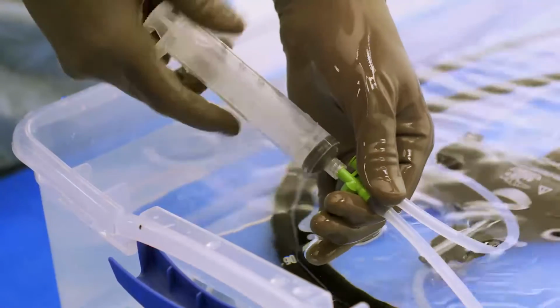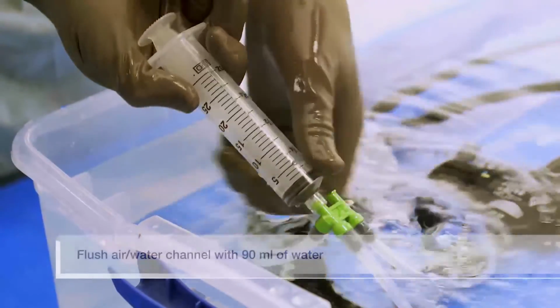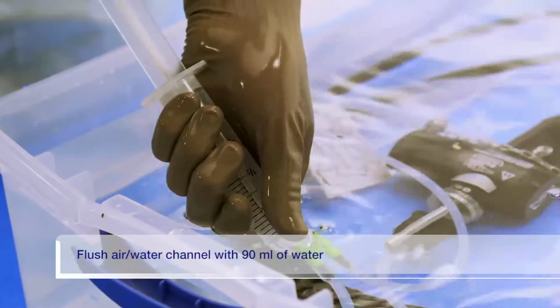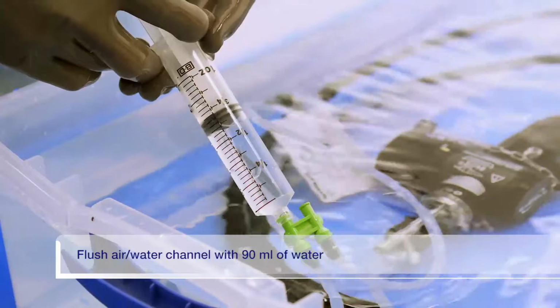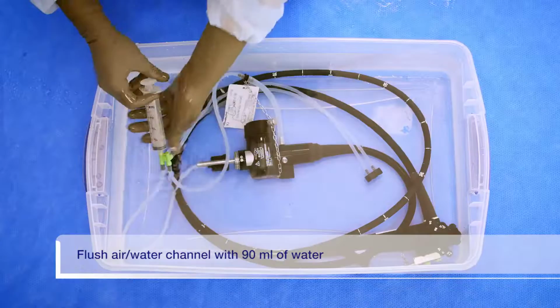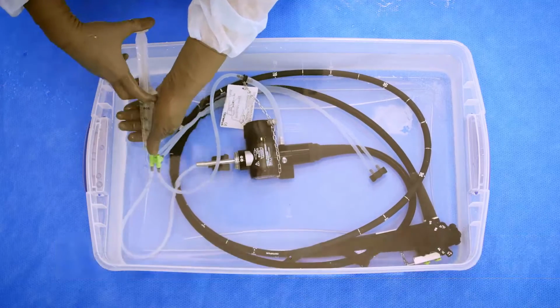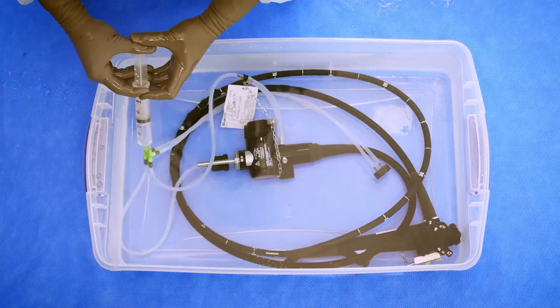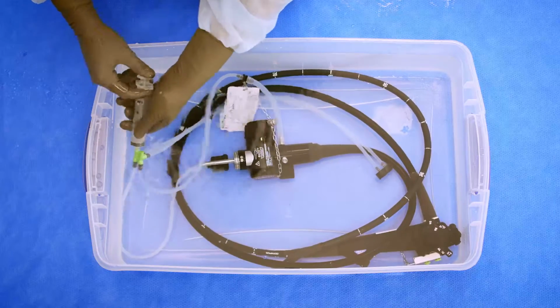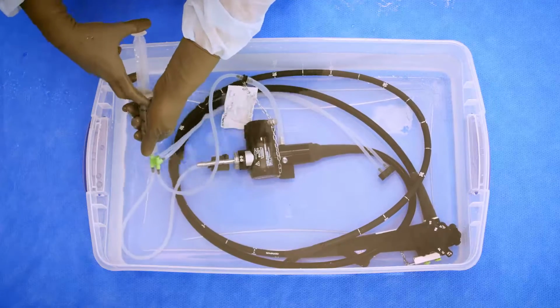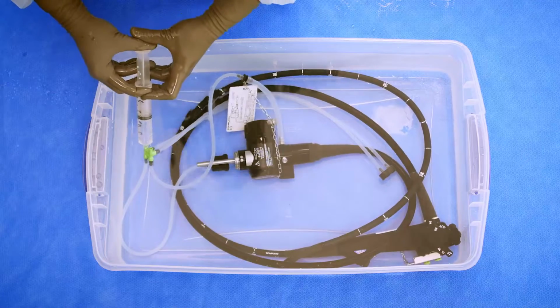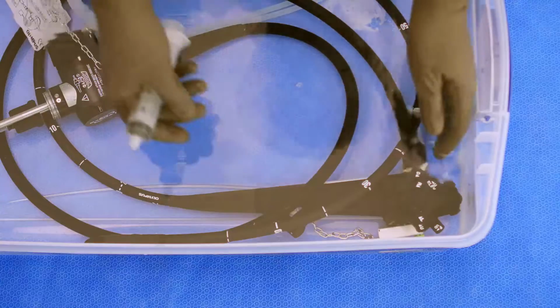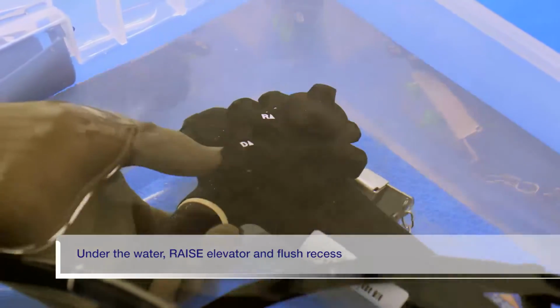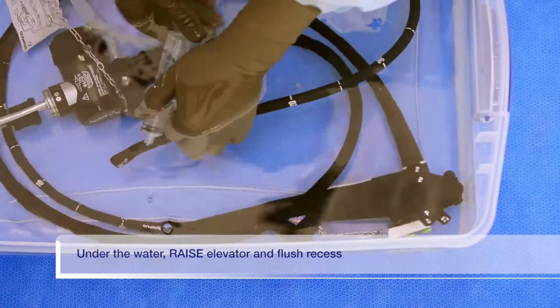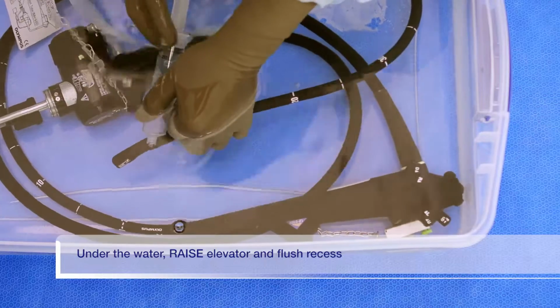Move the 30 milliliter syringe to the air-water channel port of the injection tube and flush the air-water channel with 90 milliliters of the rinse water. Raise the elevator and insert the tip of the 30 milliliter syringe into the interior of the forceps elevator recess in the rinse water. Then flush the interior of the recess with 30 milliliters of the rinse water.